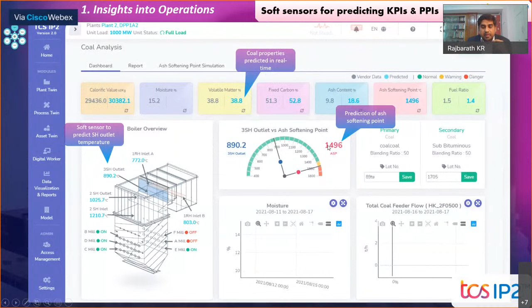So doing a root cause analysis in real time, that is done with FMEA, where we understand that heat rate loss is caused due to boiler loss and condensate loss and not because of other things. Now we can go a level deeper and identify what is causing that further, which is dry flue gas loss. In this case, boiler loss is caused due to dry flue gas loss, which in turn is because of fouling in the air heater zone. Now, again, there is a provision to go a level deeper to look at what is causing fouling in the air preheater zone, and that is where the asset FMEA is initiated, where we see that this is because of APH failure, and that's further because of bearing failure and bad lubrication. This entire diagnostics is happening in real time.